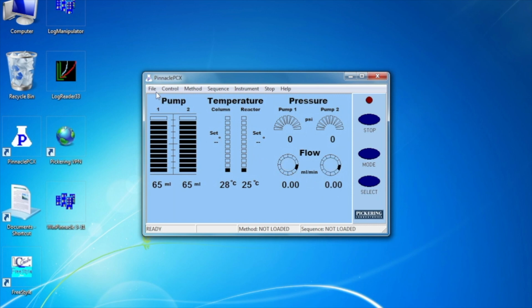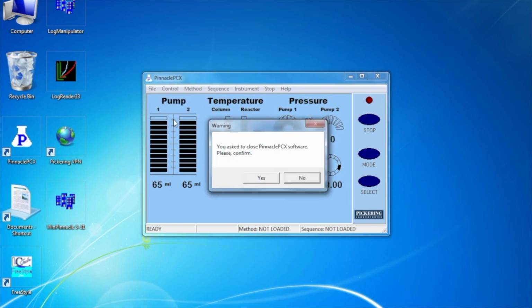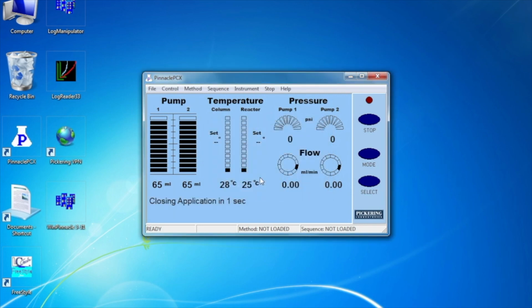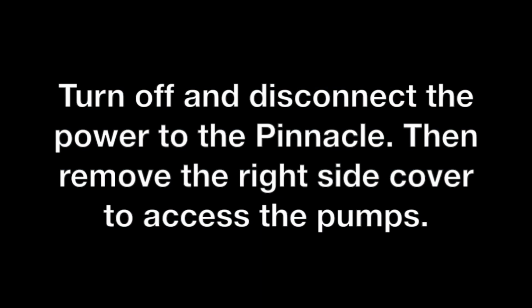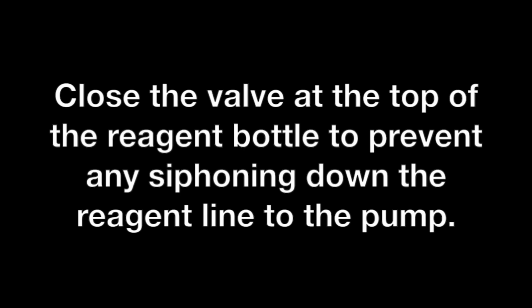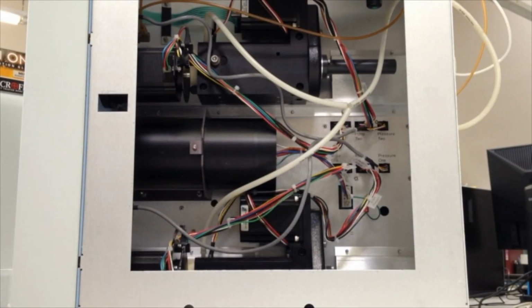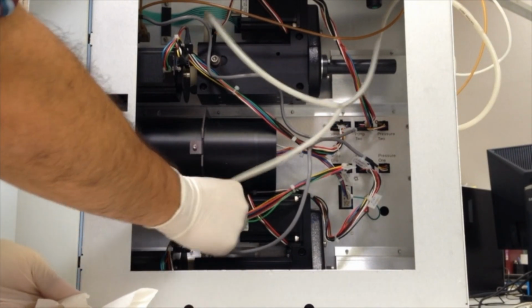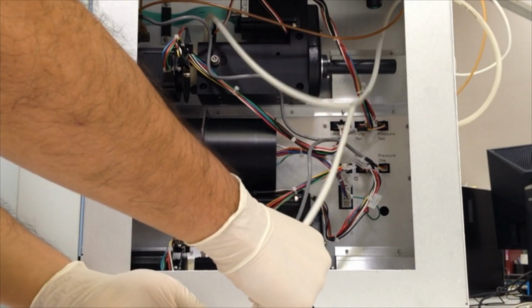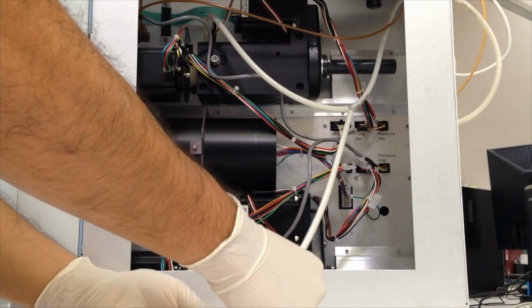Close the Pinnacle software. Turn off and disconnect the power to the Pinnacle. Then remove the right side cover to access the pumps. Close the valve at the top of the reagent bottle to prevent any siphoning down the reagent line to the pump. Remove the piston wash tubing from the piston wash port of the reagent pumps and let any excess piston wash solution drain into a paper towel.